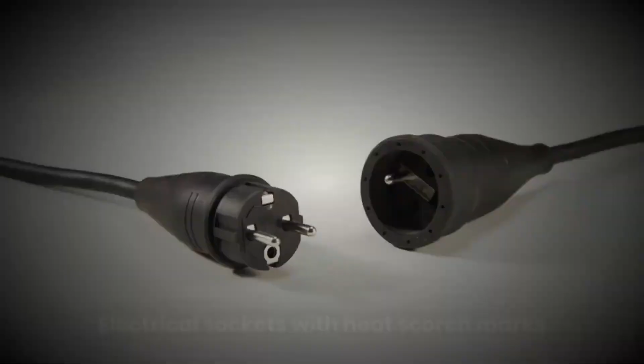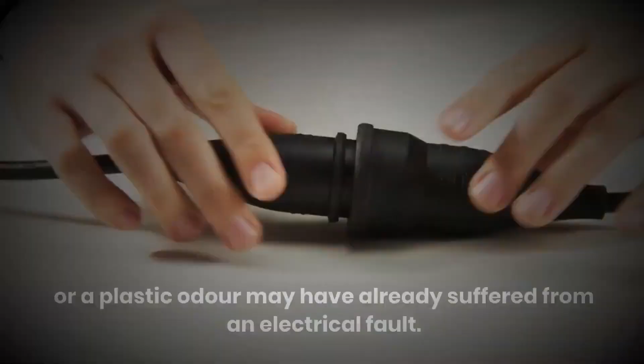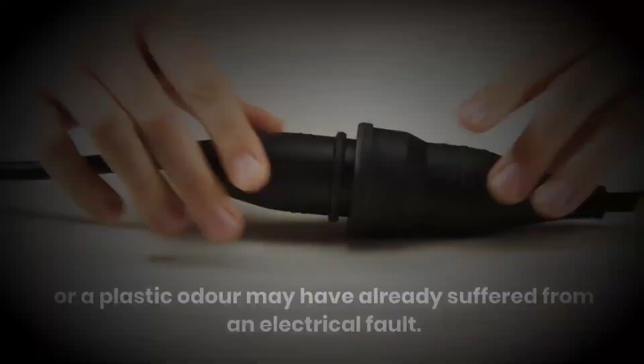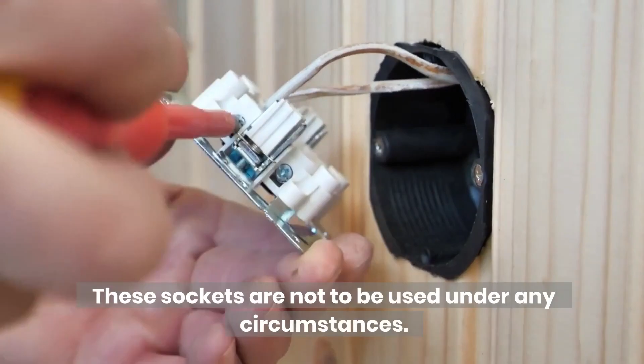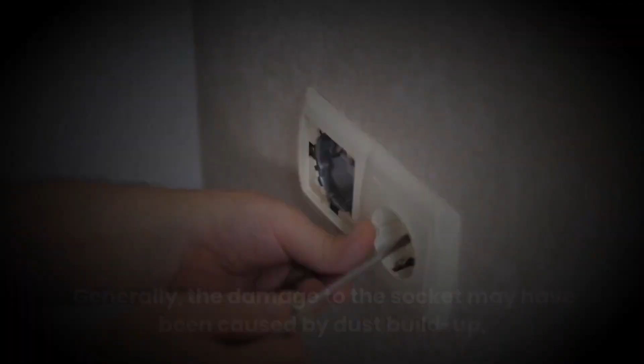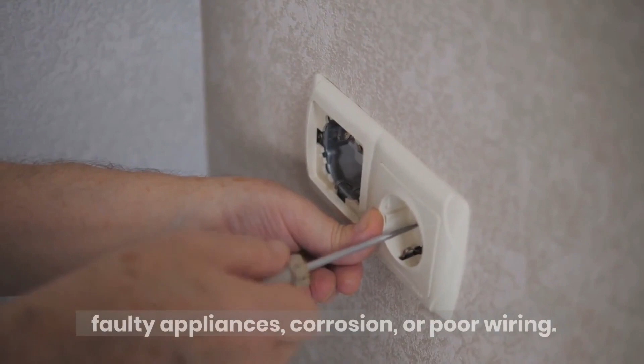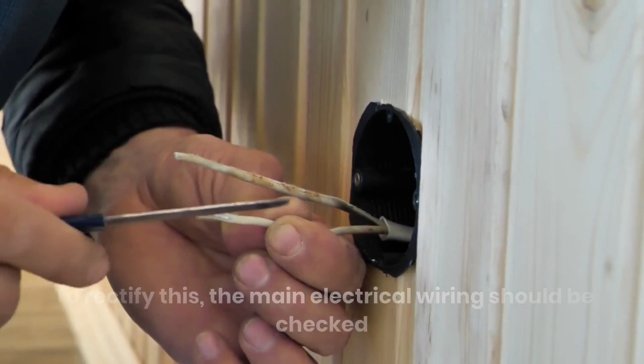Damaged sockets. Electrical sockets with heat scorch marks or a plastic odor may have already suffered from an electrical fault. These sockets are not to be used under any circumstances. Generally, the damage to the socket may have been caused by dust buildup, faulty appliances, corrosion, or poor wiring. To rectify this, the main electrical wiring should be checked and tested, as it may be the reason for the damaged socket.